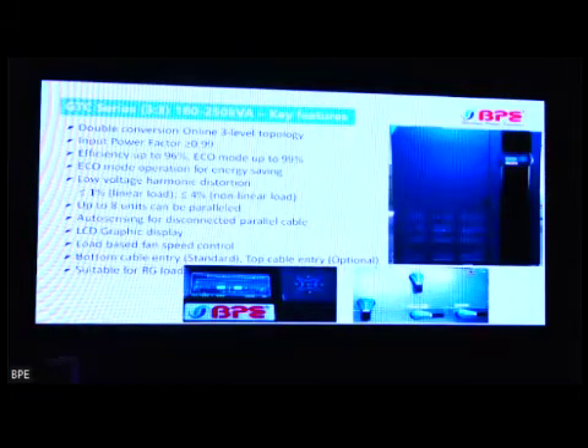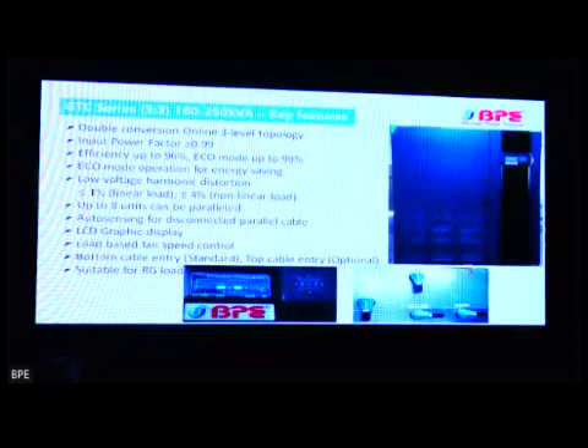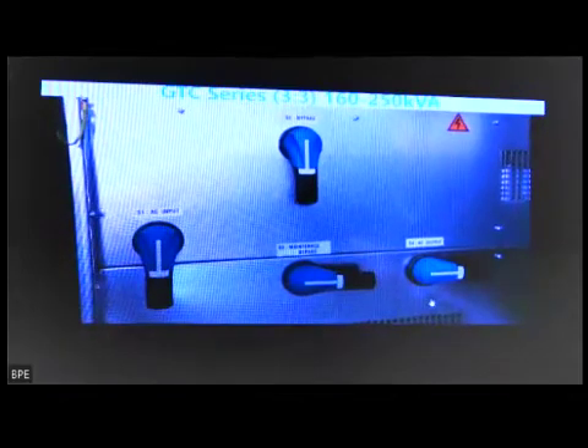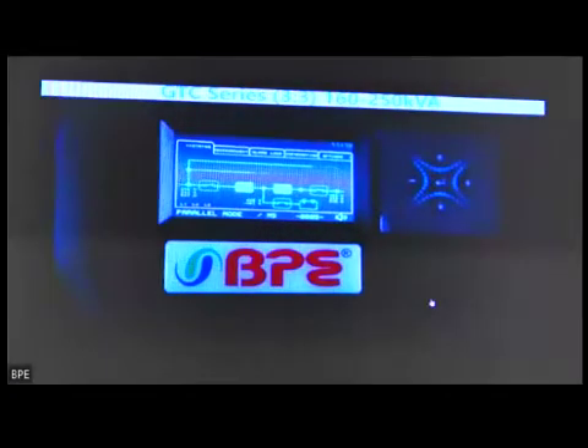Then coming to the GTC series, which is starting from 160 kVA to 250 kVA, is for the higher segment. This has got the 3-level topology. Efficiency is up to 96%. Eco mode efficiency up to 99%. It has got very low voltage harmonic distortion, less than 1% for linear loads, less than 4% for non-linear loads. And we have a video for this. It has got all the 4 switches for input, output, bypass and manual bypass. Ports for parallel communication ports. Large LCD display.